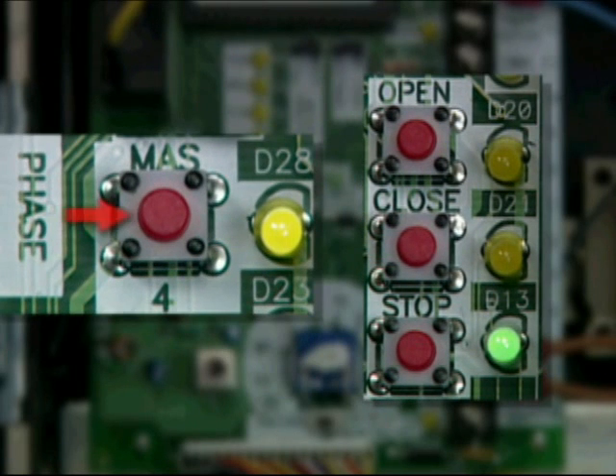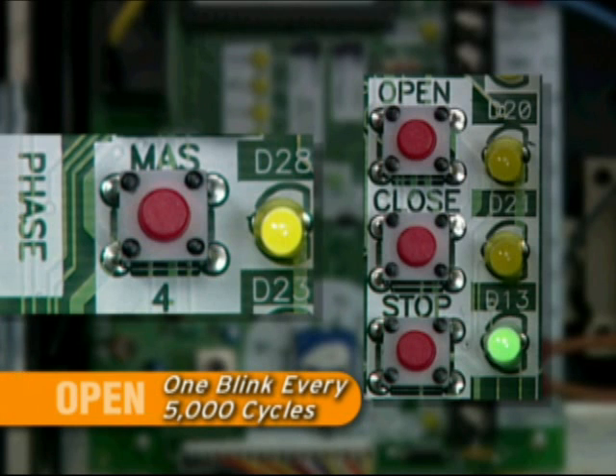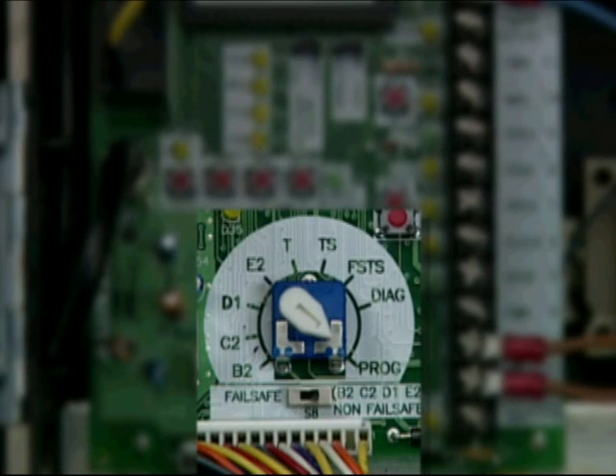Press the MAS button on the logic board to complete programming. At this time, the open and close LEDs will blink to indicate programmed month and cycle schedule. The open LED will blink once for every 5,000 cycle increment programmed. The close LED will blink once for every 3-month increment programmed. To finish programming, turn the selector dial back to the desired wiring type.